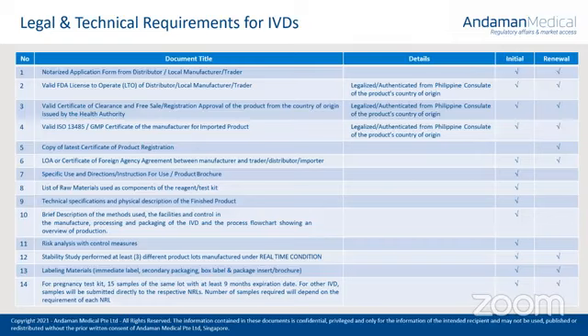Brief description of the methods used, the facilities and control in the manufacture, processing and packaging of the IVDs, and the process flow chart showing an overview of the production. So similar to general medical devices, the process flow and manufacturing procedure shall also be included, including its process control. Risk analysis with control measures, so either FMEA or risk management report, these are acceptable to FDA.